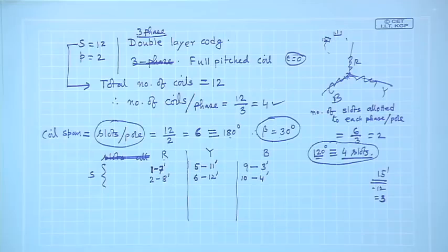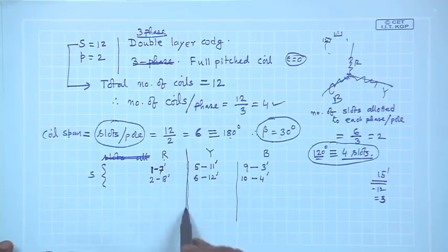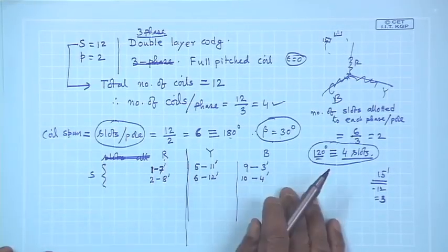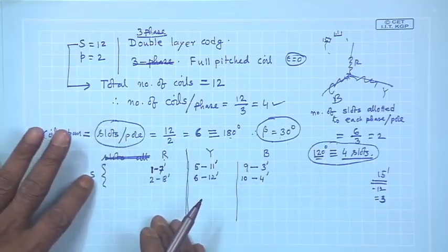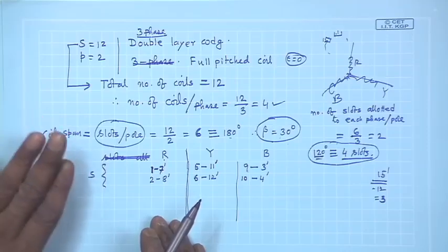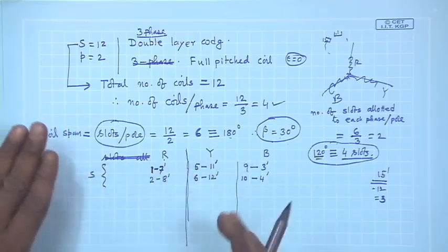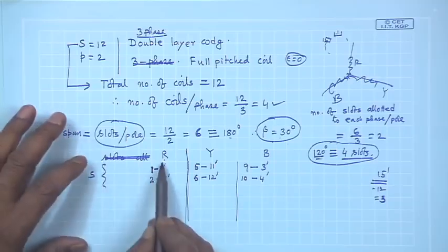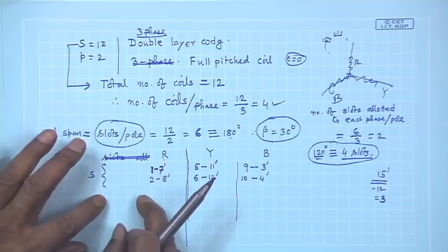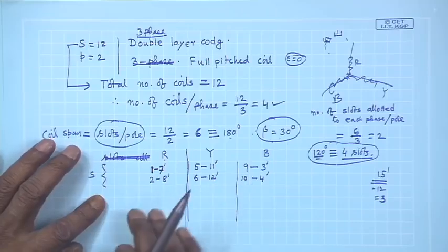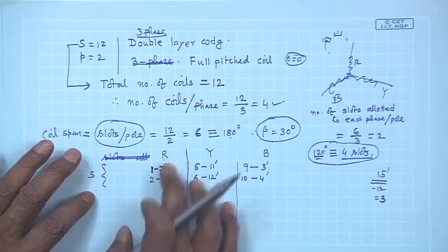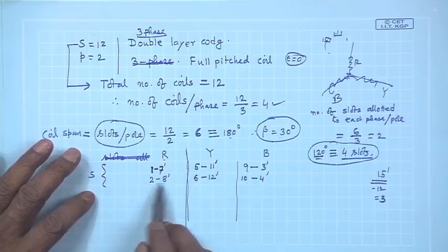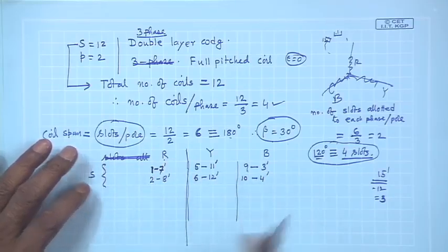Understood? So, what I am doing is, I am making the windings like this. It is a 2 pole machine. Suppose under 1 pole, this writing of south north is for my convenience, but anyway, 2 slots I have allotted to R phase. Then if you have started the winding from slot number 1 for R phase, 1 7 dash, 2 8 dash, 5 11 dash, and so on.